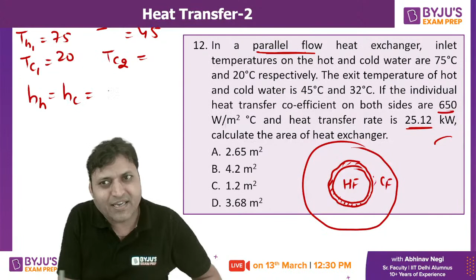Now what can be done? So we can write Q is equal to U into A into delta Tm. We can find out LMTD. TC2 is 32 now. We can find out LMTD from this because it is a parallel flow. We need to find out U and LMTD. First of all, calculate LMTD for parallel flow. It is TH1 minus TC1, 75 minus 20, 55, minus 45 minus 32, 13, upon natural log of 55 by 13. That is LMTD.